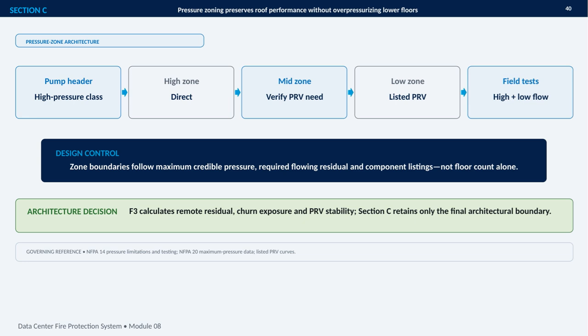The low zone uses a listed PRV where required. These decisions are then verified through field testing at both high-flow and low-flow conditions, because stable performance must be demonstrated across the operating range. The detailed calculations, including remote residual pressure, churn exposure, and PRV stability, are completed in F3. Section C retains the final architectural boundary. The governing references are NFPA 14, NFPA 20, and the applicable listed PRV performance curves.